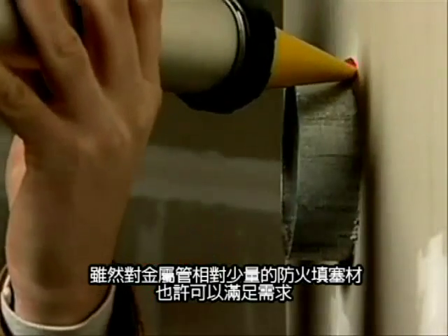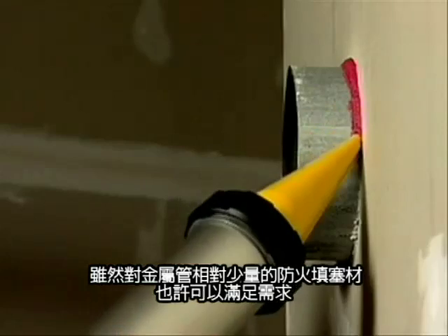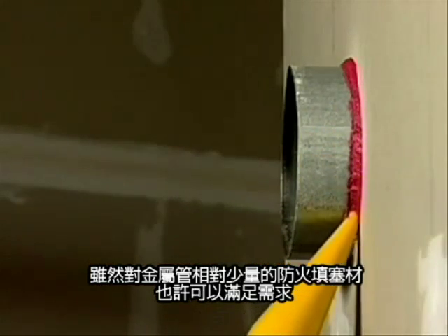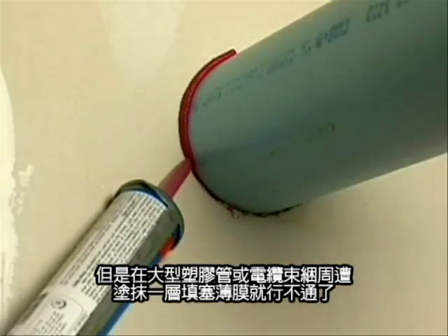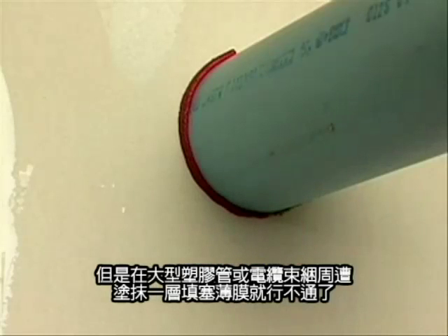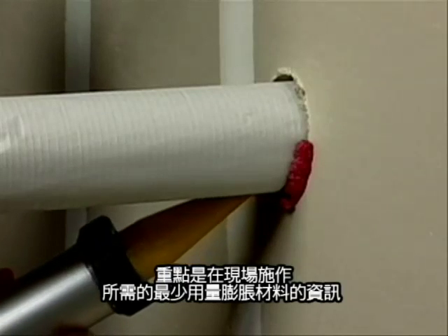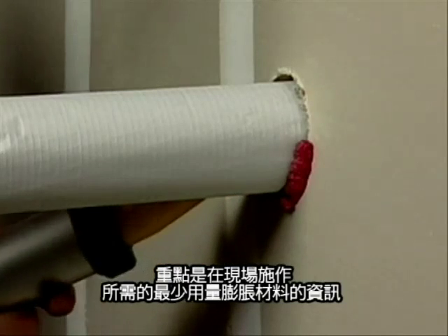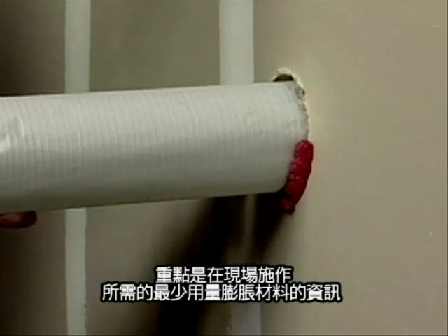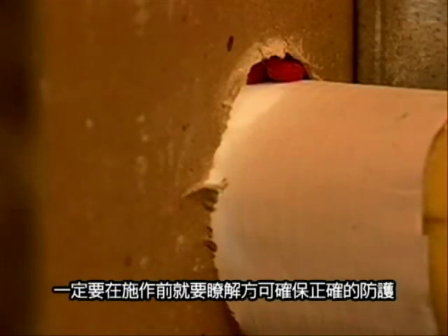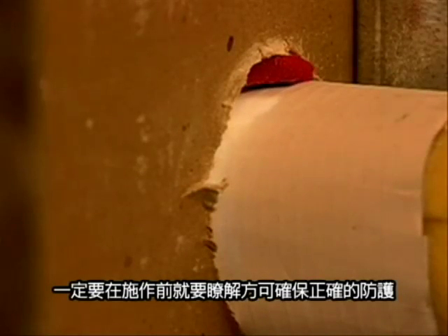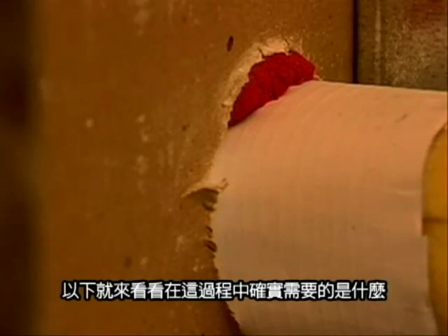While a relatively small bead of fire stop sealant may be adequate for a metallic pipe, smearing a thin film of caulk around a large plastic pipe or bundle of cables simply won't work. The point is that a prescribed minimum amount of intumescent material is needed to do the job, and this information must be known prior to installation to ensure adequate protection. So let's explore this process and see exactly what's required.